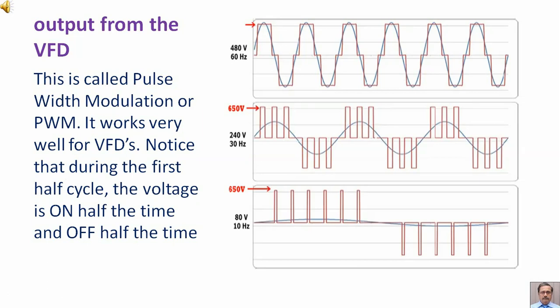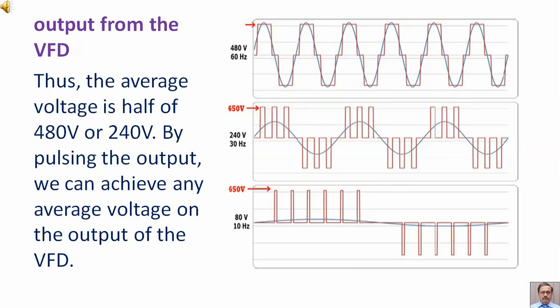This is called pulse width modulation or PWM. It works very well for VFDs. Notice that during the first half cycle, the voltage is on half the time and off half the time. Thus the average voltage is half of 480 volts or 240 volts. By pulsing the output, we can achieve any average voltage on the output of the VFD.